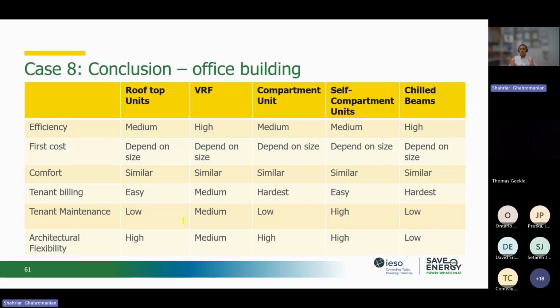So if we compare these systems, it's good to take a look at a rooftop unit, a variable refrigerant flow, a compartment unit or self-compartment unit, and chilled beams. The efficiency of the VRF and the chilled beams is the highest, and the rooftop units and the compartment units are going to have a medium efficiency. The first cost depends on the size of the system, but typically VRF is more expensive. The comfort of all of these, heat pumps or variable refrigerant flow, is going to be similar.